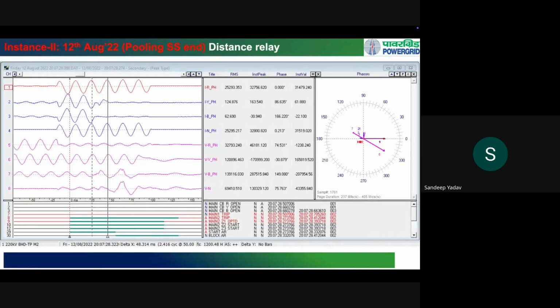Yeah, so this is an example of an R phase to ground fault. So if you take a look at R phase, and this is the grid side, the initial three channels, R, Y, and B phase currents. The R phase current is 25 kiloampere. So this is the fault point where the dotted line is, and after the fault, the fault contribution from the grid side in the faulty R phase is 25,000 ampere or 25 kiloampere, which is expected.